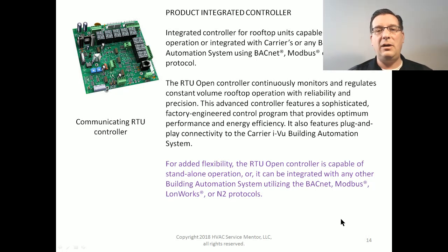This is an example of a sophisticated controller from Carrier for our rooftop unit that can be either communicating through a number of different language protocols, or it can operate all by itself. So one of the things that we'll do in the commercial world is, okay, I don't know if you're able to talk to the network properly or not. Therefore, I'm going to take you off the network and see if you operate all by yourself. And if you do, then I know that you're having a network communication issue, and I'll look there. If you don't, then I know that you, in fact, are faulty, and I'm going to replace you, and then your new replacement should be able to communicate to the network and operate just fine.